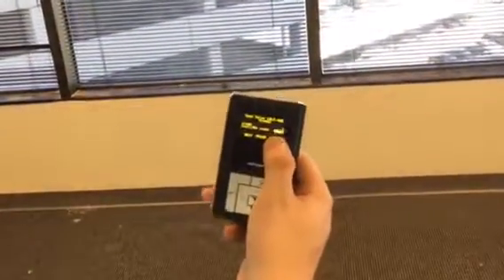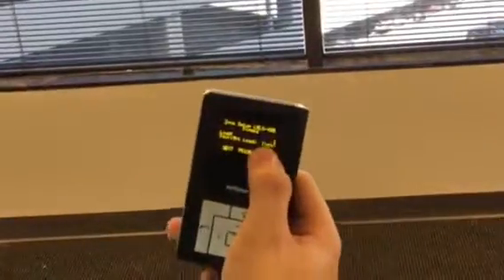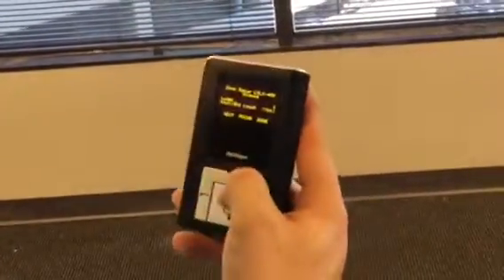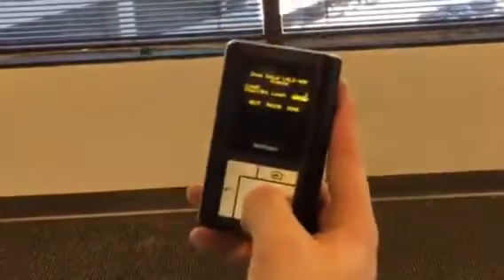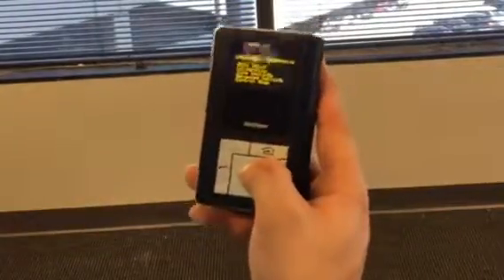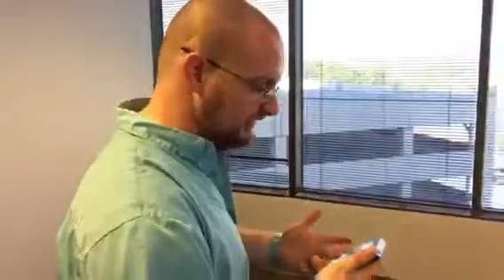So the first thing we want to do is zone setup, and it's a dim. I can make it switch, tri-level, or bi-level. Okay? So it's going to cut on what load is currently displayed there. It's actually going to flash it so you can identify and see where it is. Again, by default, out of the box, load 1 is always assigned to that daylighting zone. If we go to load 2, by saying next, it's not assigned. So if I wanted it to work off the daylighting, I would assign that zone, and I'd scroll down to next, or to done, and I'll press select, and voila, I've now assigned, just like binding a switch and binding a sensor, I have bound that load as the daylighting zone.